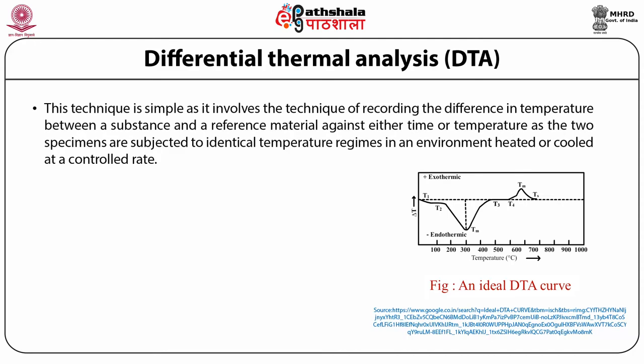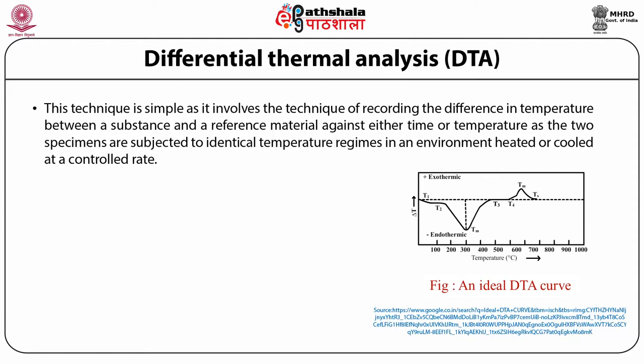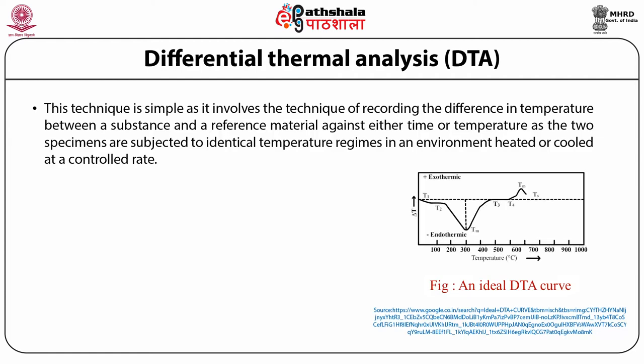We shall study these techniques one by one. Differential thermal analysis is simple — it involves recording the difference in temperature between a substance and a reference material against either time or temperature, as the two specimens are subjected to identical temperature regimes in an environment heated or cooled at a controlled rate. A differential thermogram records the difference in sample temperature T_S and reference temperature T_R, plotted as a function of time, sample temperature, or furnace temperature T_F.